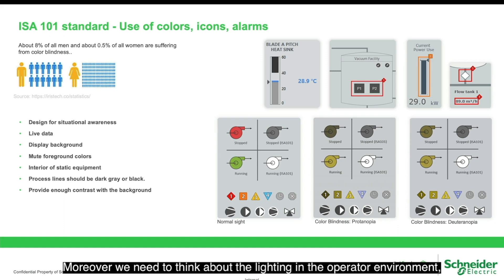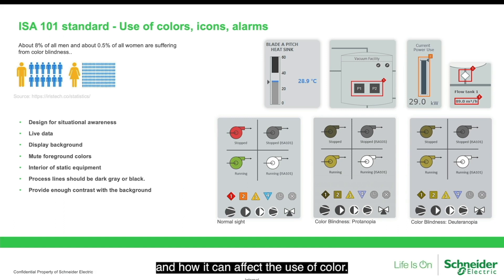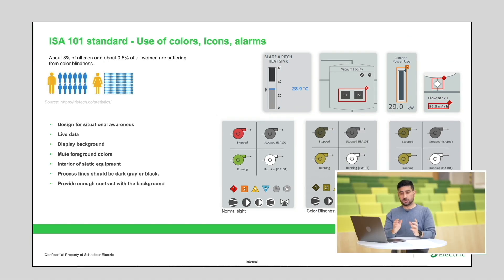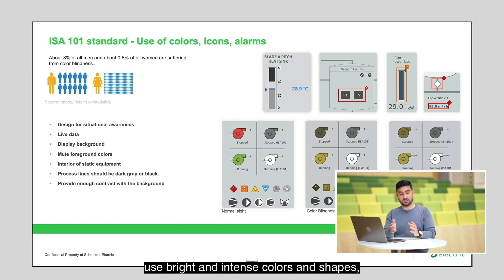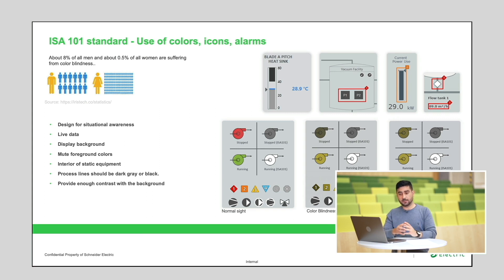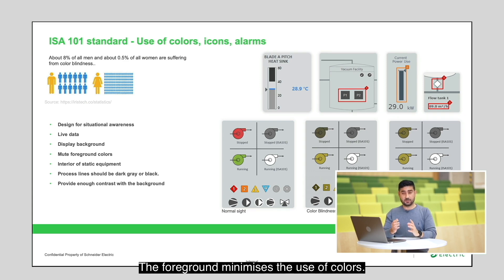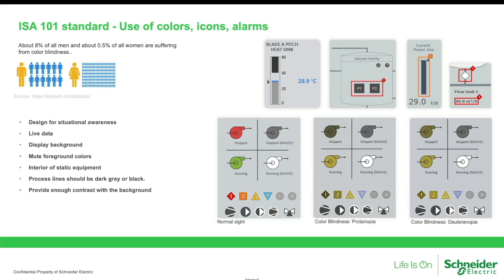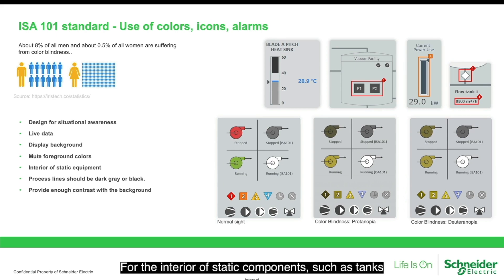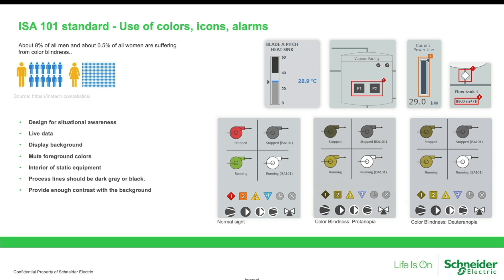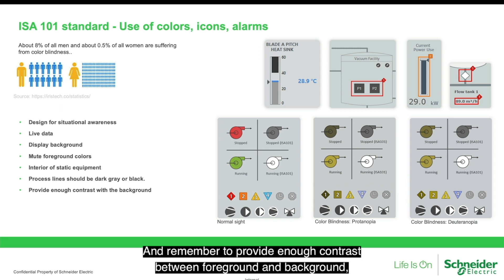Moreover, we need to think about the lighting in the operator environment and how it can affect the use of color. So when we use color, we need to design for situational awareness, especially in alarm situations. Use bright, intense colors and shapes to direct operator awareness. Use cool colors for live data. The display background should be a non-alarm, unsaturated gray color. For the foreground, minimize the use of colors for interior static components such as tanks — use the same background color as the display. The process line should be gray, dark gray, or black.